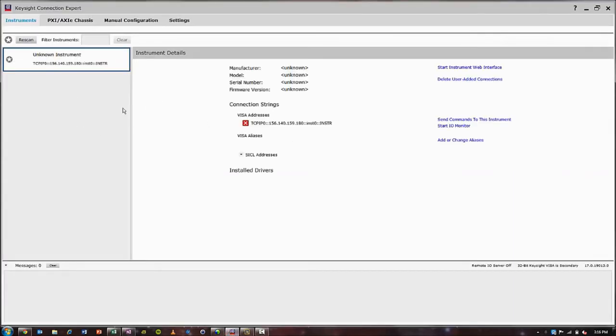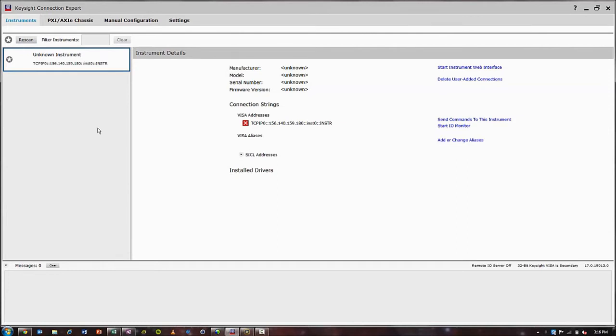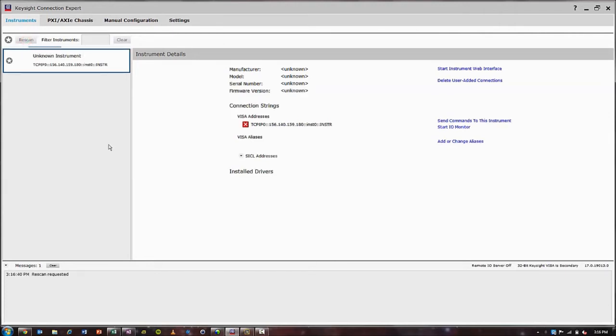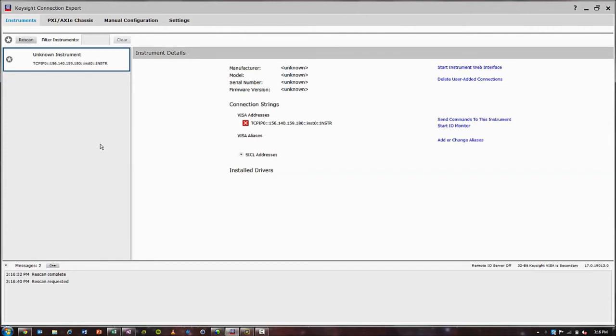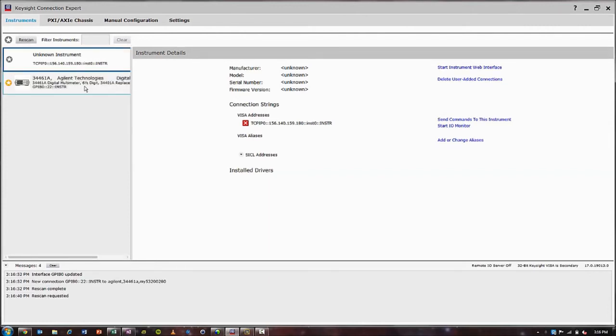This program allows you to see your instrument when it's been connected. What I'm going to do is plug the USB side of my GPIB to USB converter into my PC and then Keysight Connection Expert will discover the instrument. So let's rescan. Great.